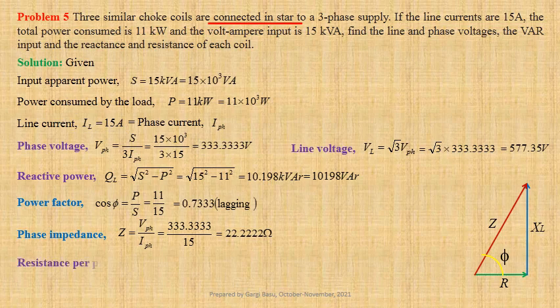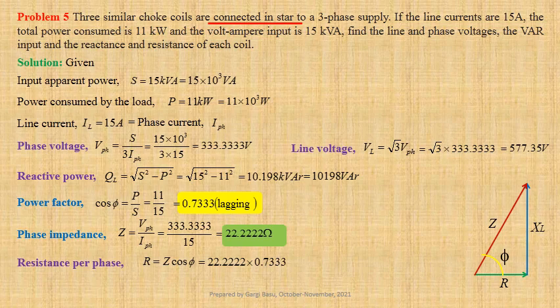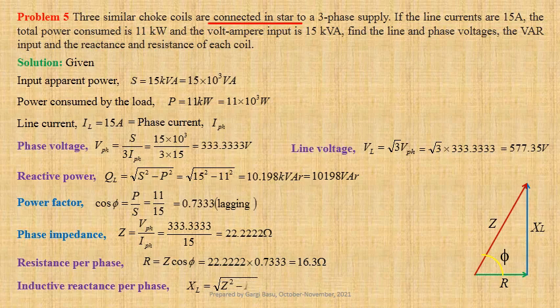From impedance triangle, resistance per phase R equals Z into cos phi; using values 22.2222 into 0.7333 equals 16.3 ohm. Inductive reactance per phase XL equals root over Z squared minus R squared; using values root over 22.2222 squared minus 16.3 squared equals 15.1 ohm.